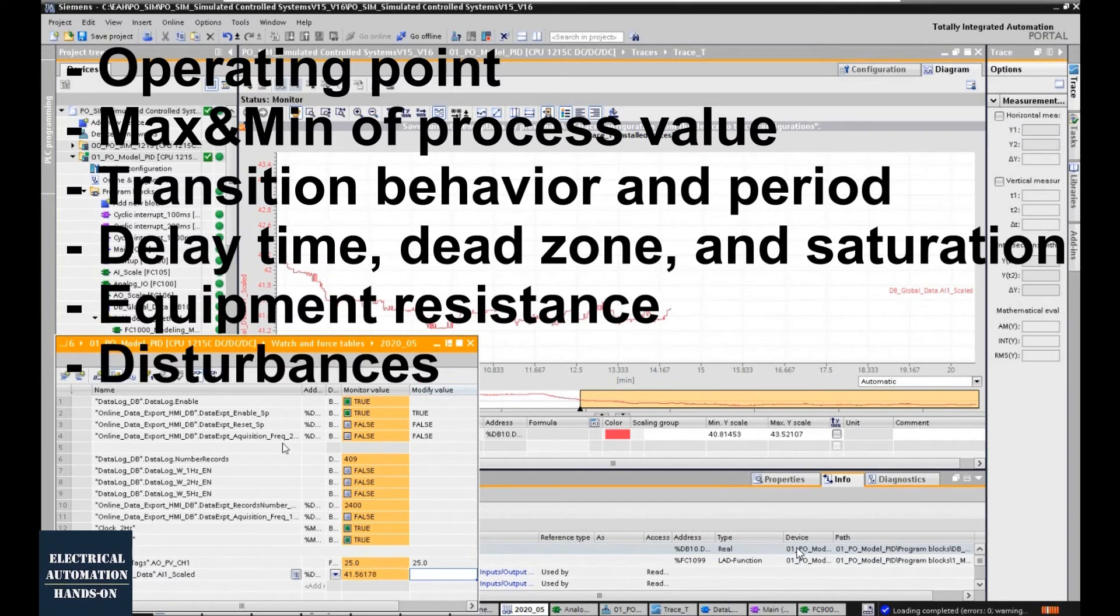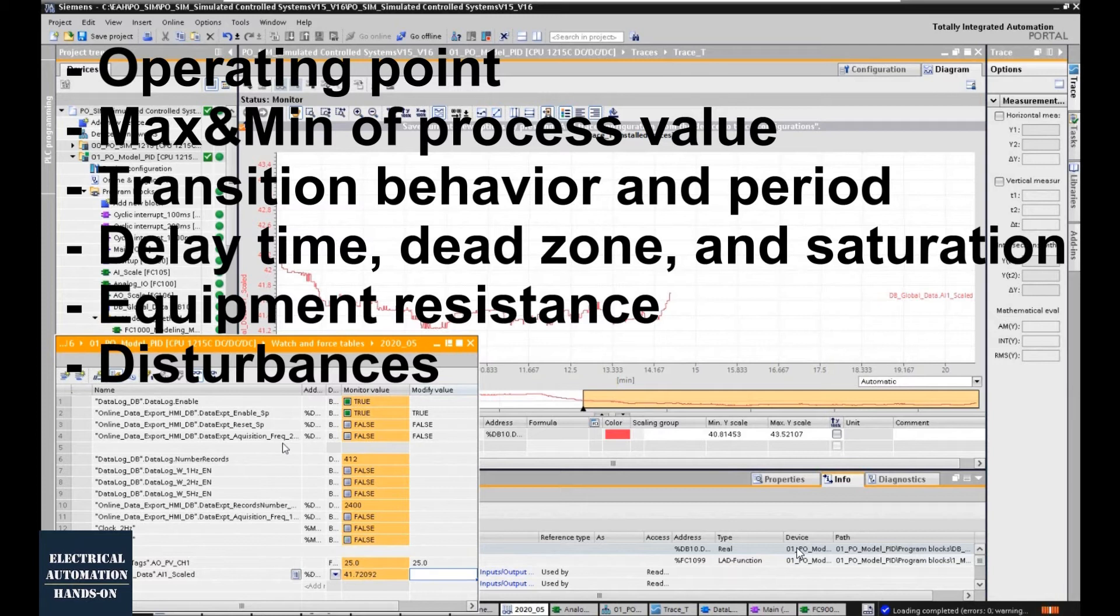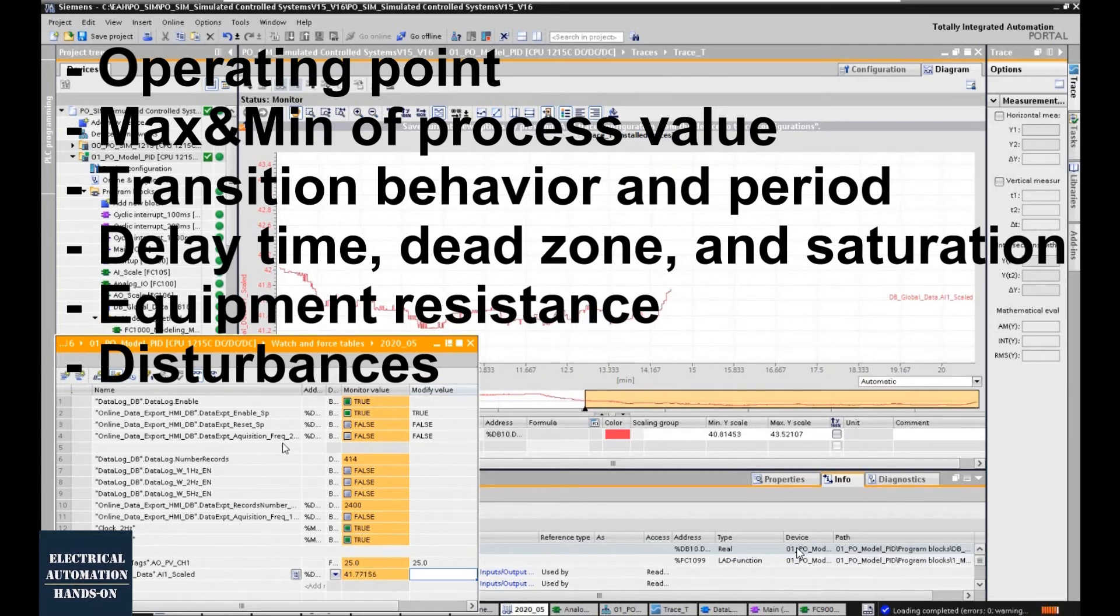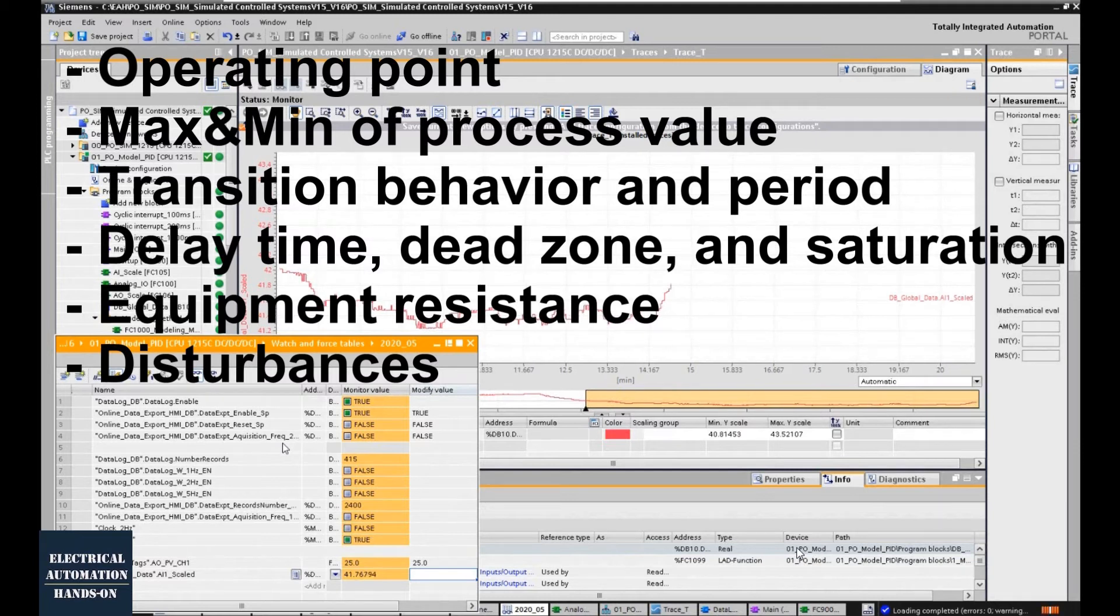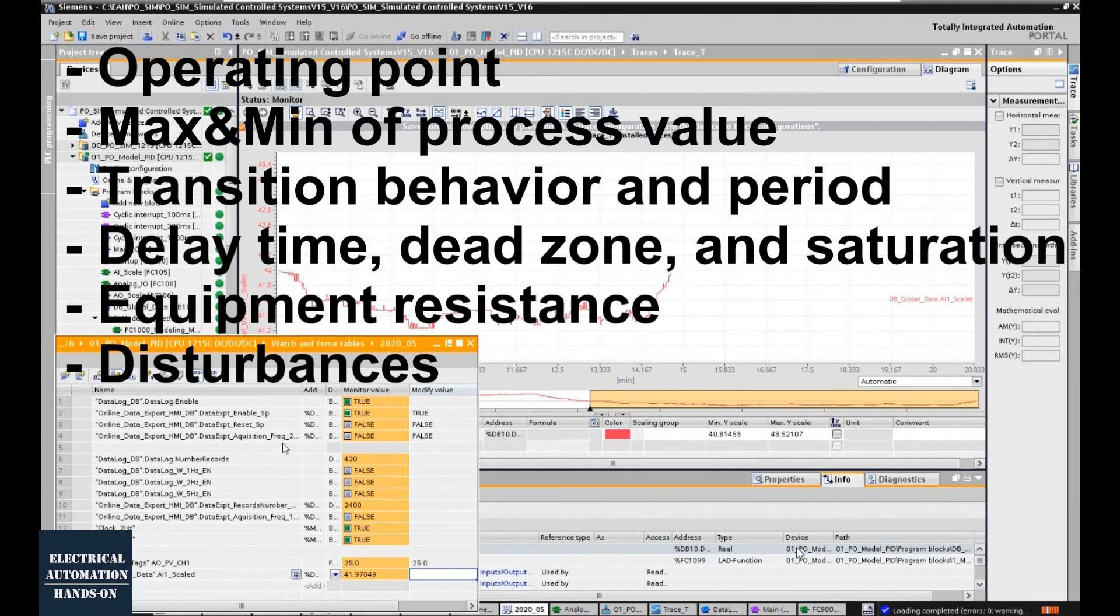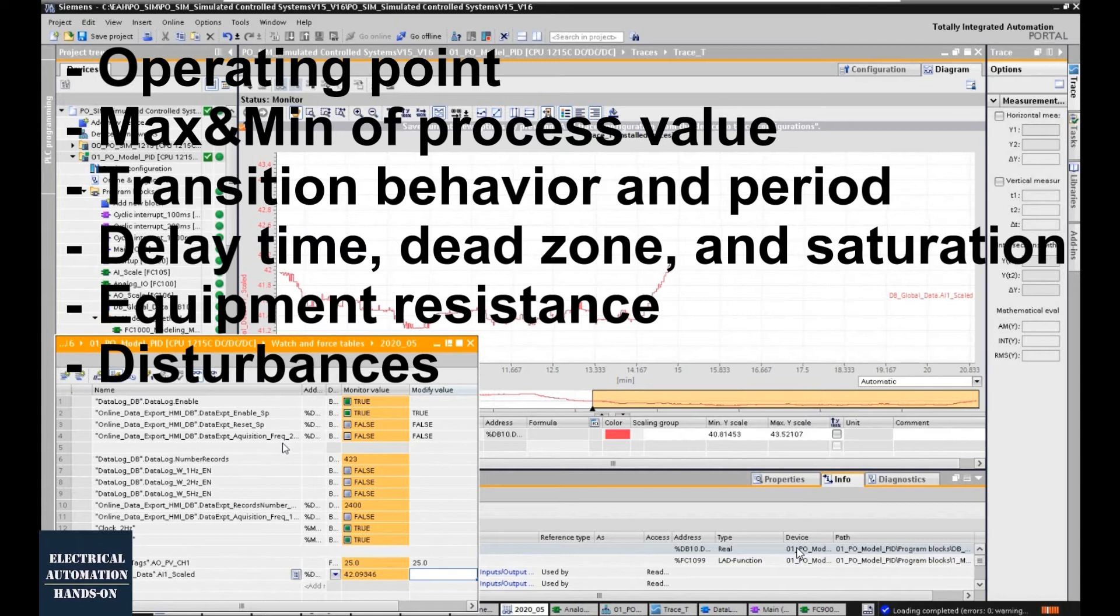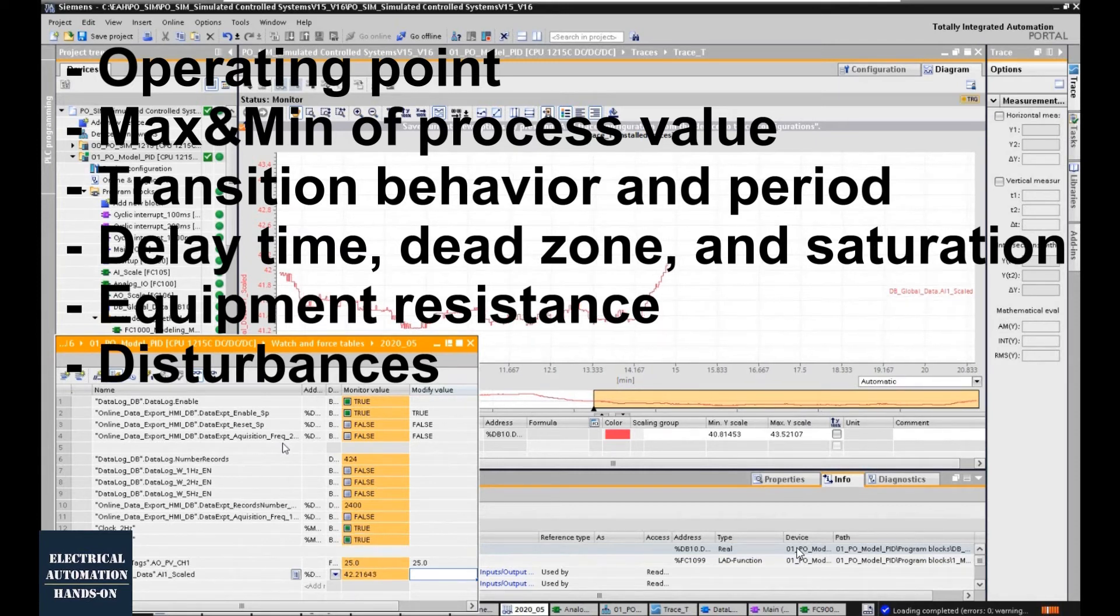The next item is the disturbance of your system. You need to figure out what the main disturbance variables for your system are. What the main problem caused your system got a disturbance. Because, as a PID closed-loop system, its working target is the setting point, but actually it's working against the disturbance. So it will affect the closed-loop controller control performance. Also, it's the main issue for the process value stability.